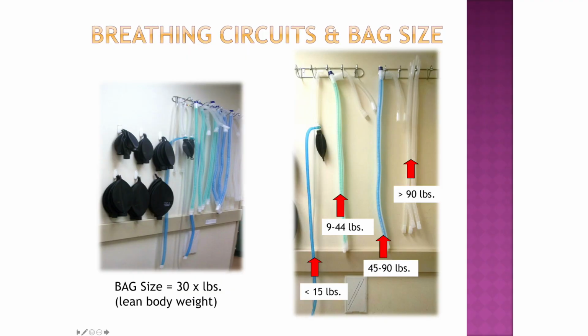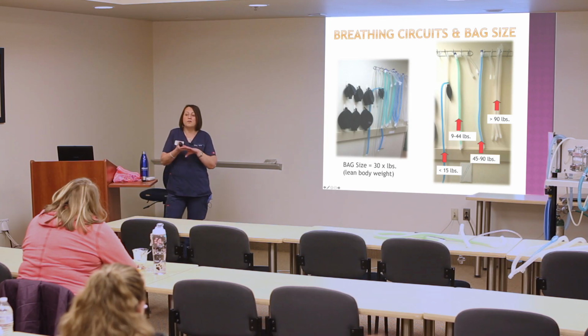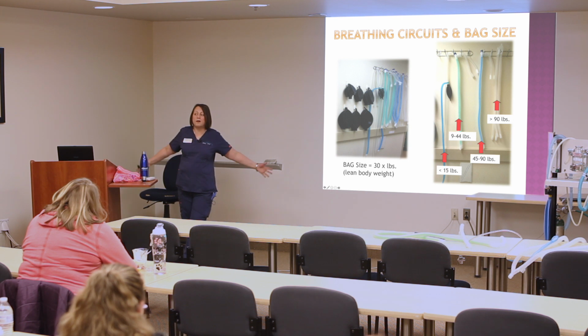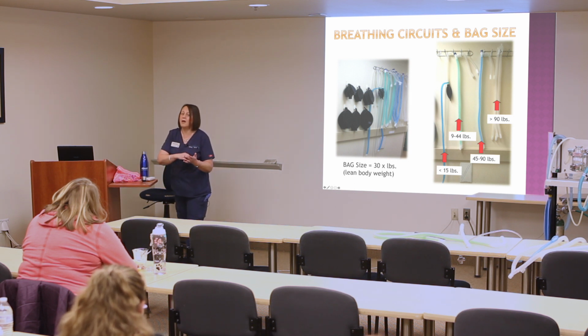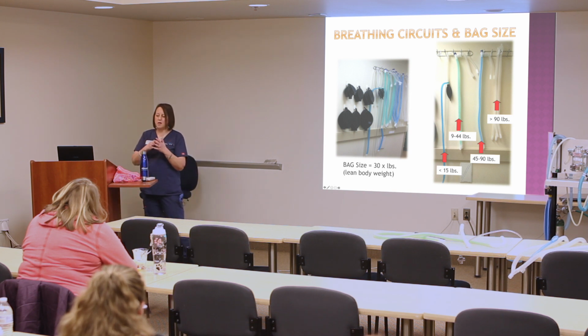And so that does make sense to me that using a non-rebreather would be an efficient way to mask down an animal, because you really don't need the soda-sorb assembly. You're not really trying to scrub out carbon dioxide or anything like that for those. And then the bag is 30 times the weight in pounds. And let's remember, people, that this is based on lean body weight. So if I suddenly became 500 pounds, I don't suddenly have the lung capacity of a pony, right? I still have the lung capacity of, I go with 125, okay? So you calculate my lean body weight, and that's the bag size I should be using.